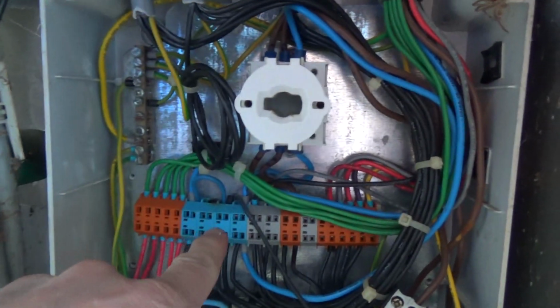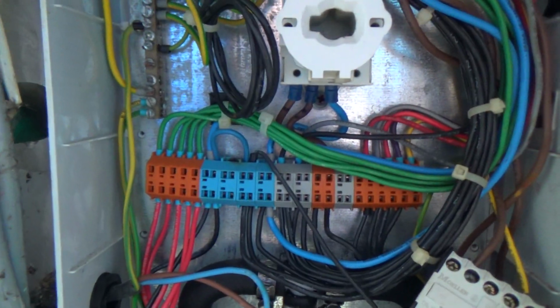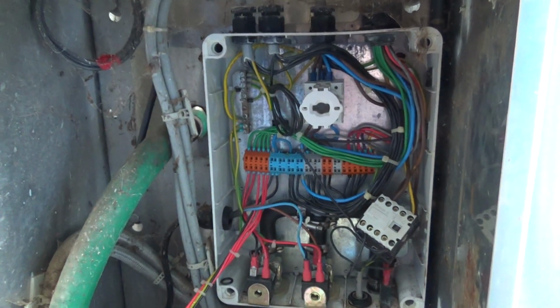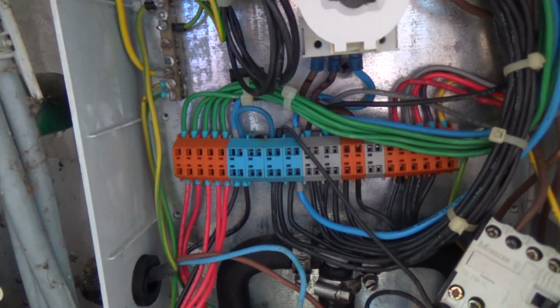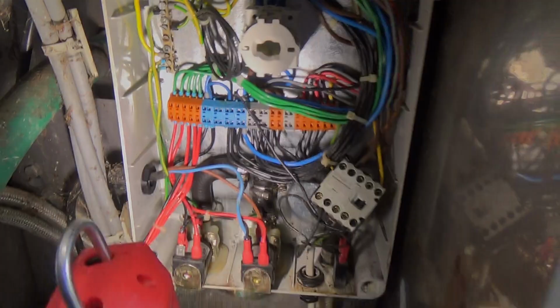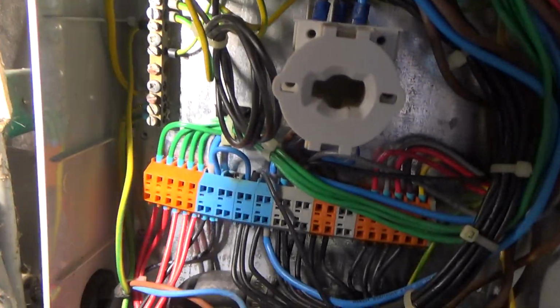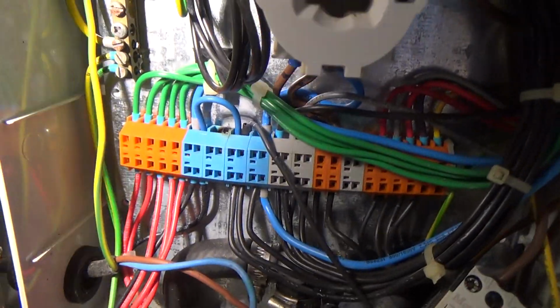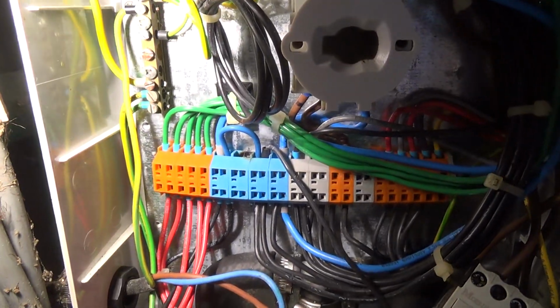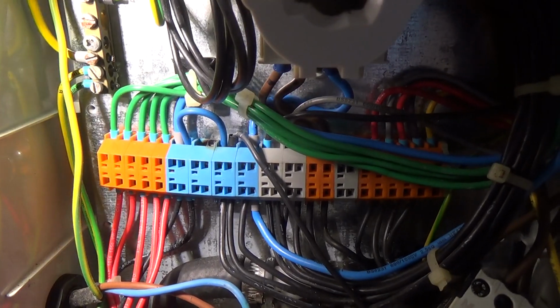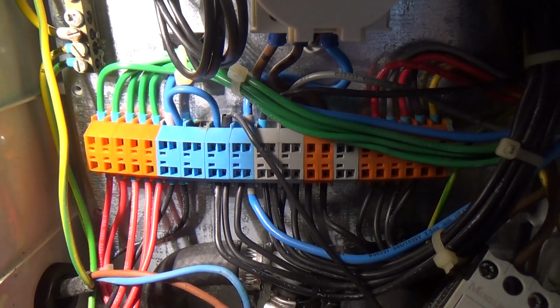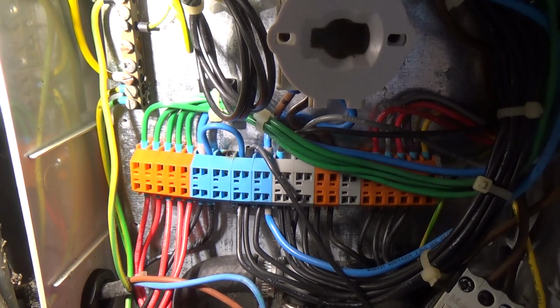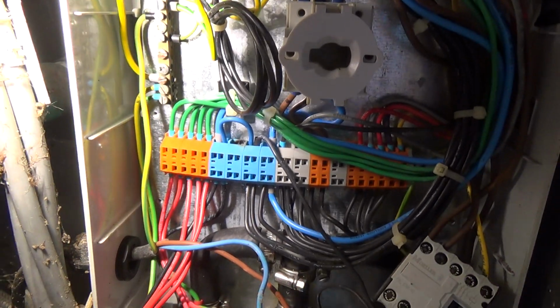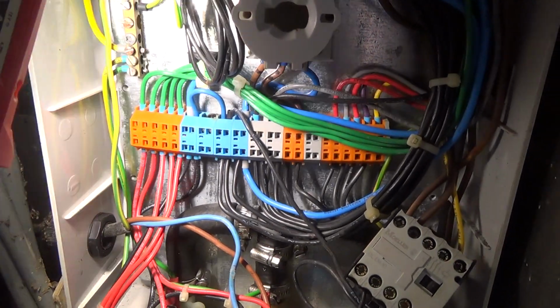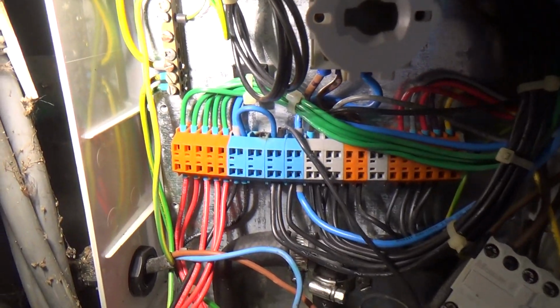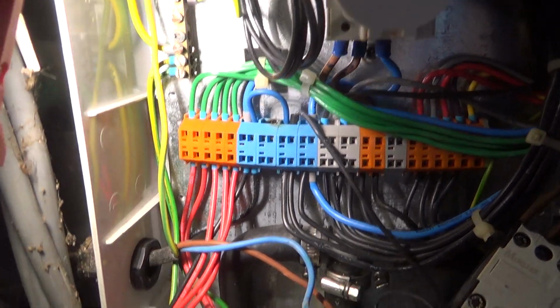Ooh, burning. We've got some burning wires. Haha, that might be it. That might be it, and I think that's on a neutral. I'll get a torch. No, that looks to be historic. I was thinking there's where that black wire comes in at the top. There's a number on it, and I thought the number was a bit of ash from where it had been burning, but it's just a number. So that centre one's burnt out.